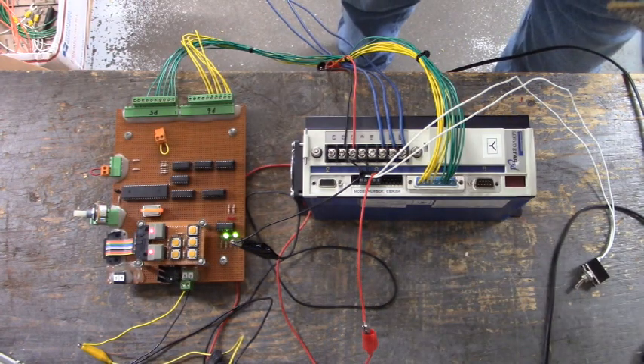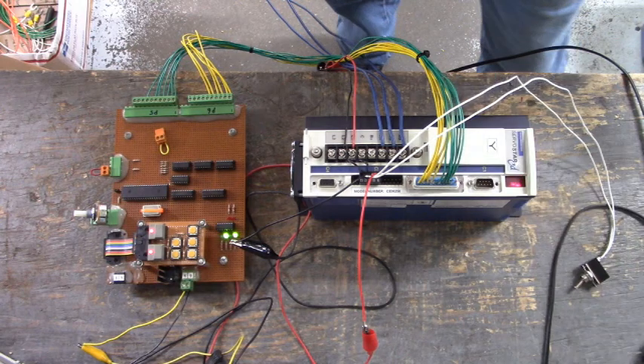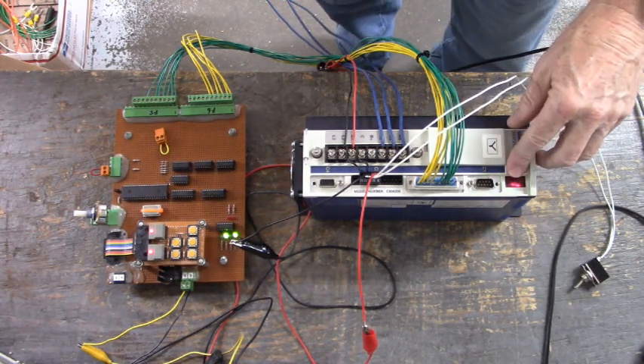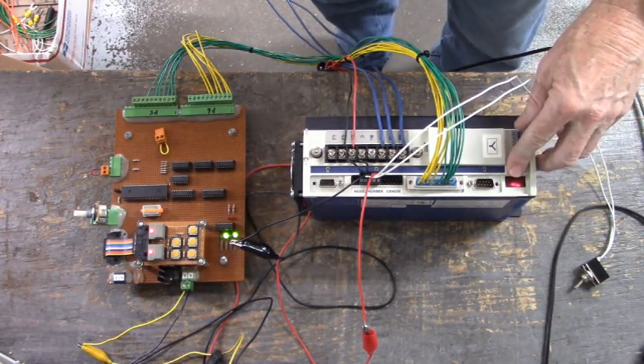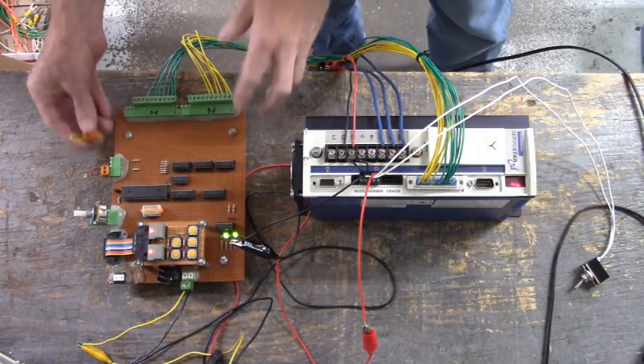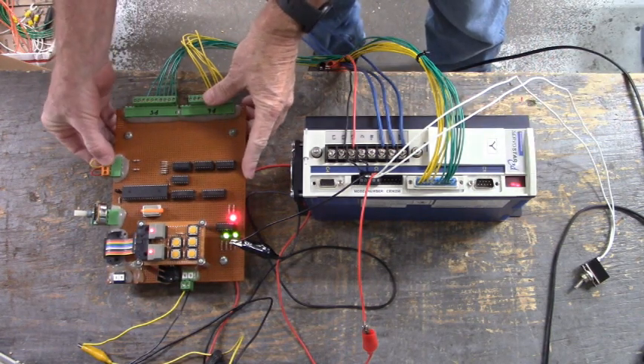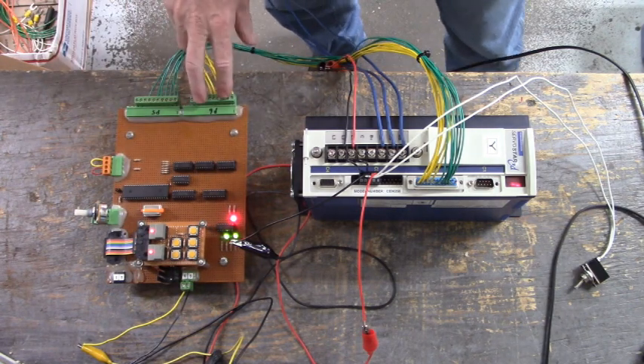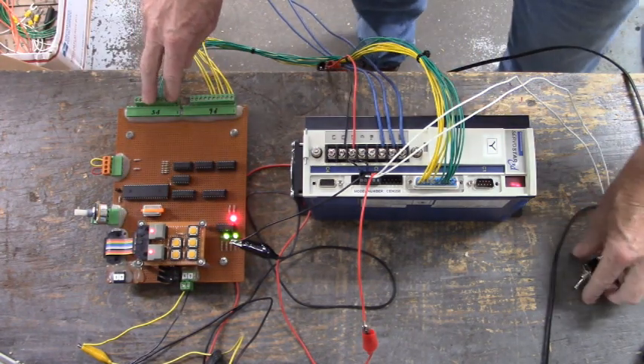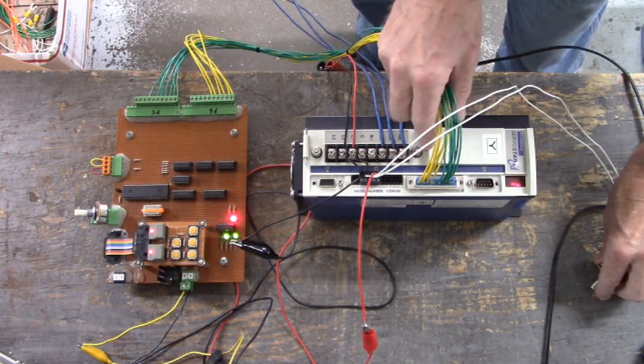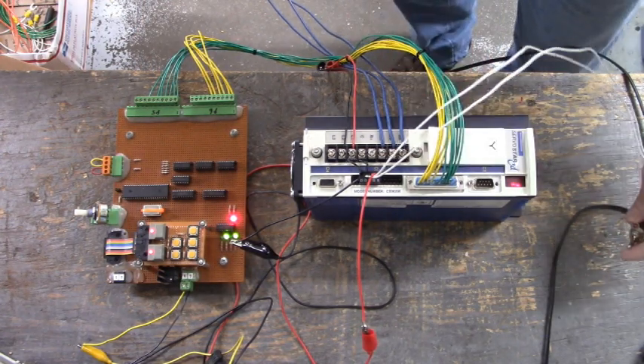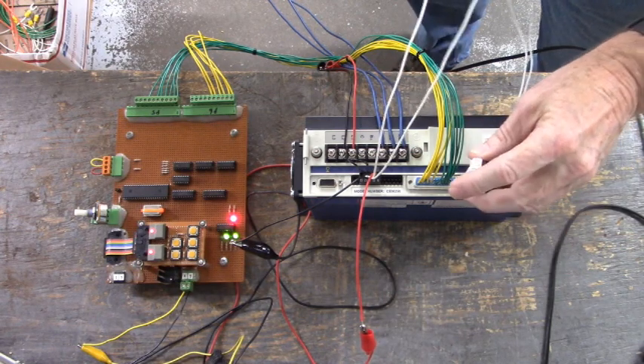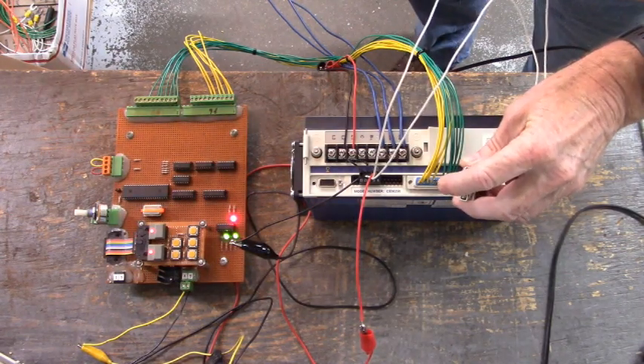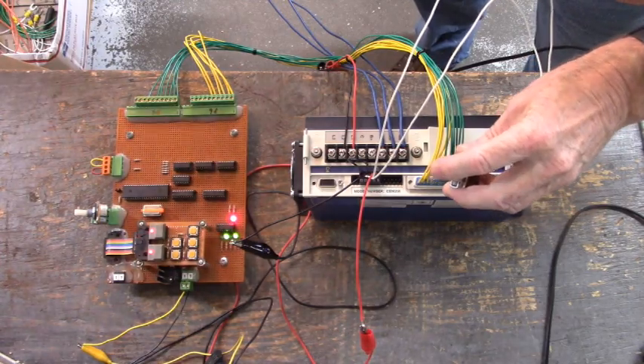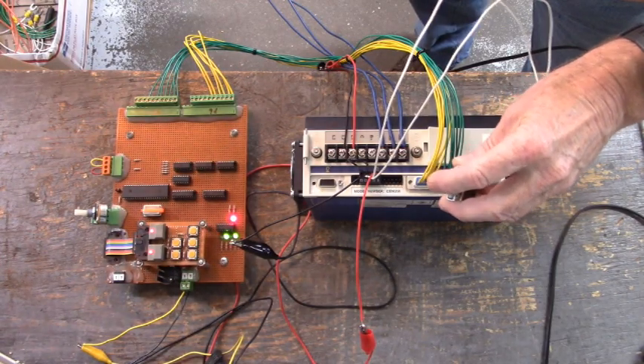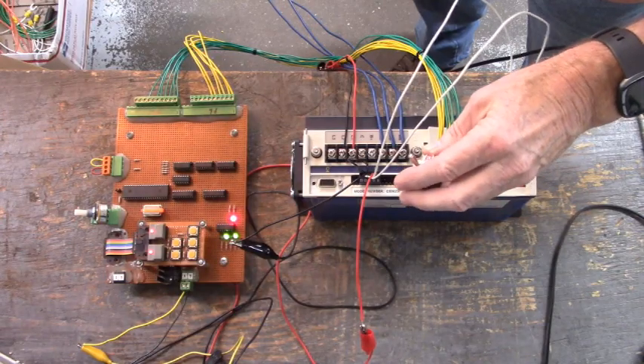We're going to turn on the drive, and we come up with the number 1 in the 7-segment display. Now we're going to enable the output of the incremental encoder and Hall Effect that's being input to the C2 connector, and this switch right here is going to enable the output. Now the light bulbs are sequencing through their rotation.